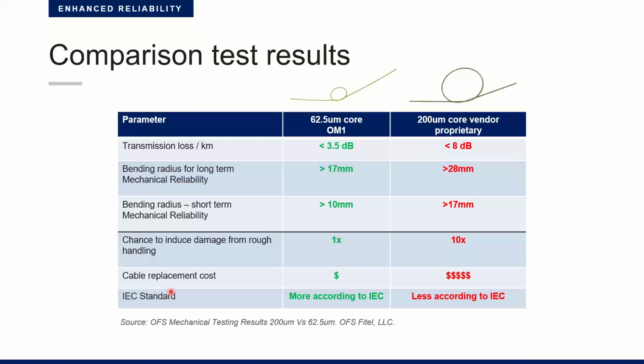It's just when you lead the fiber through the transformer, when you route it with the 62.5, you're just more flexible. And summarizing all that, chances to induce damage from rough handling are 10 times higher with the 200 micrometer fiber. And replacement costs are also much higher with the 200 micrometer fiber. Why? Because I said in the previous slide, the 62.5 fiber is a standard from the telecom, and everything which is a standard keeps you as a customer flexible.